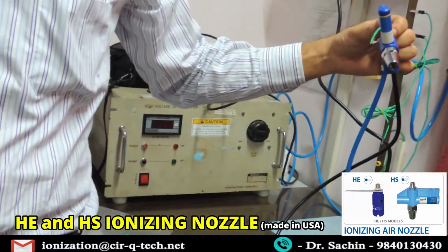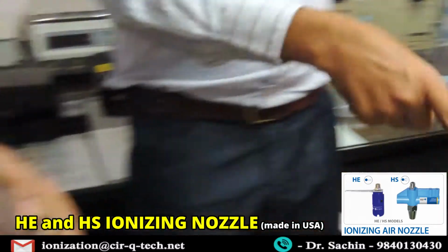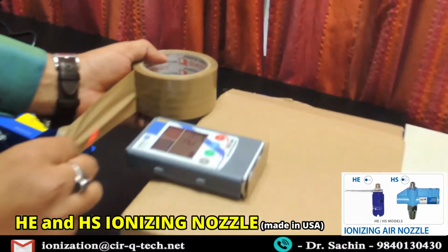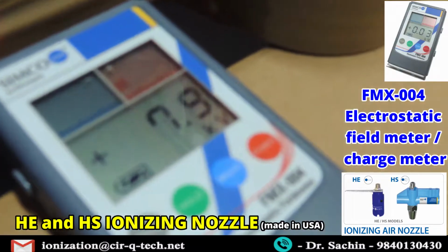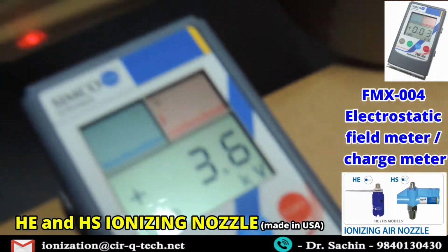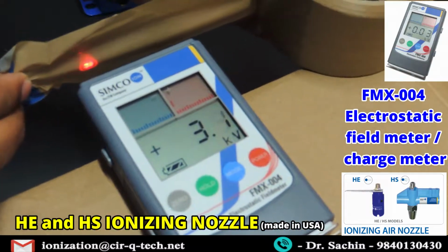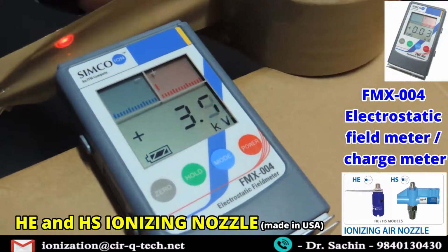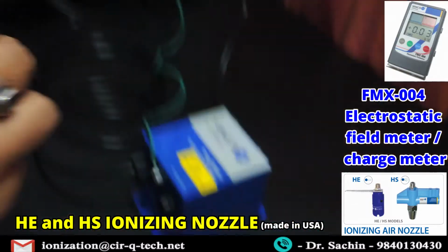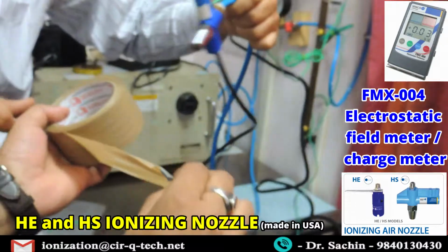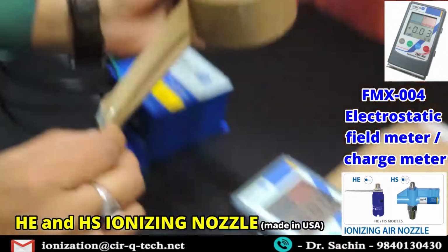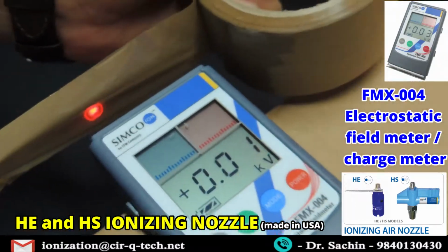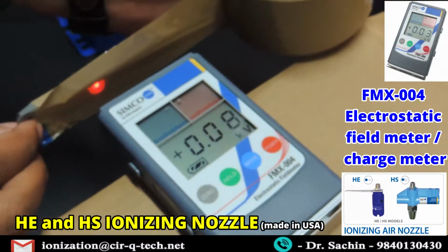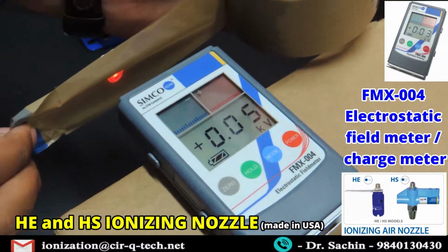My colleague here will just use a tape. We are using a packing tape, and what he is doing is separation and showing the static measurement on it. Okay. Now we'll use a nozzle to remove the static charges. Okay, and there you go. The readings have almost neutralized, with hardly more than about 100 volts of charge on it.